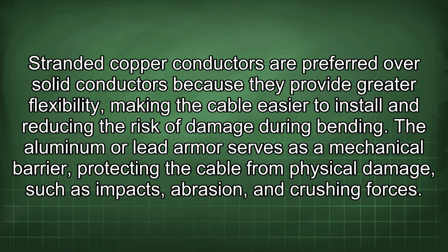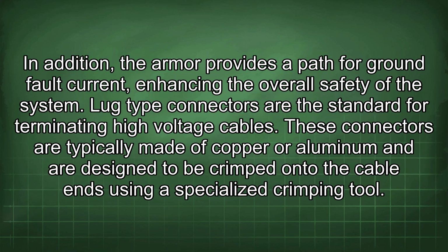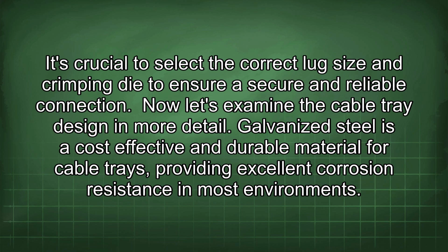Stranded copper conductors are preferred over solid conductors because they provide greater flexibility, making the cable easier to install and reducing the risk of damage during bending. The aluminum or lead armor serves as a mechanical barrier, protecting the cable from physical damage such as impacts, abrasion, and crushing forces. In addition, the armor provides a path for ground fault current, enhancing the overall safety of the system. Lug-type connectors are the standard for terminating high-voltage cables. These connectors are typically made of copper or aluminum and are designed to be crimped onto the cable ends using a specialized crimping tool. It's crucial to select the correct lug size and crimping die to ensure a secure and reliable connection. Now let's examine the cable tray design in more detail.